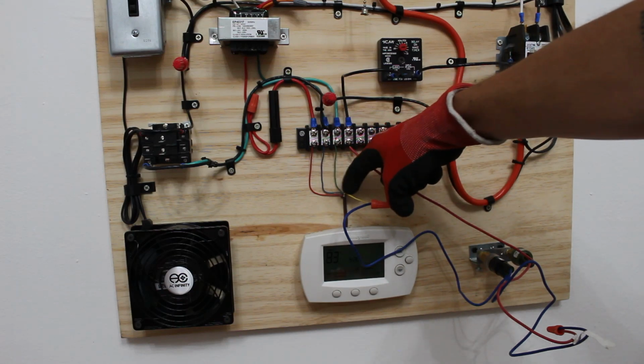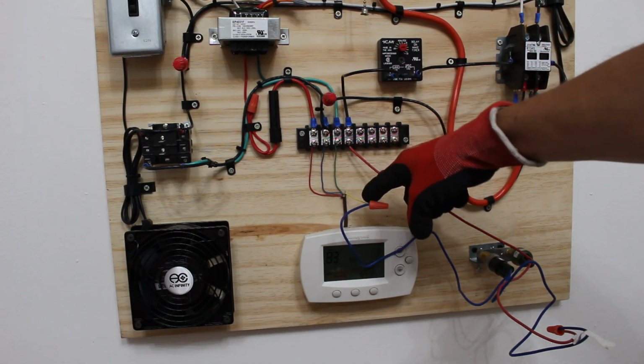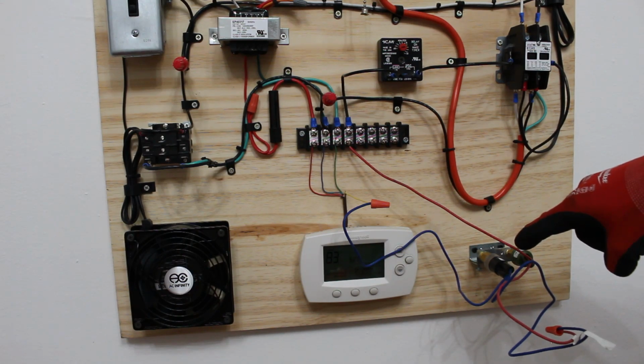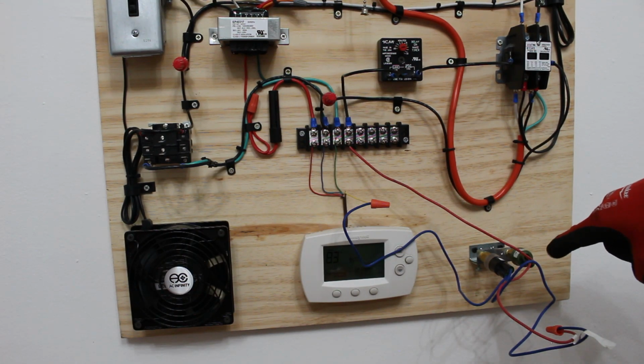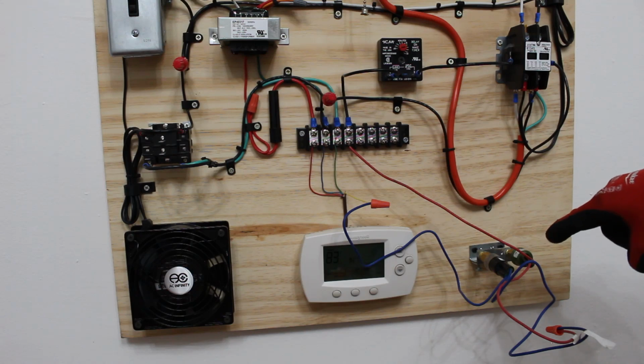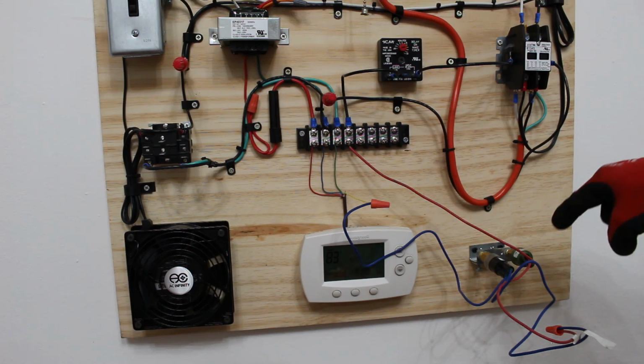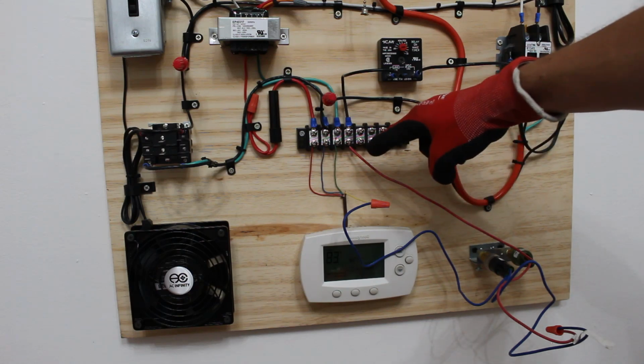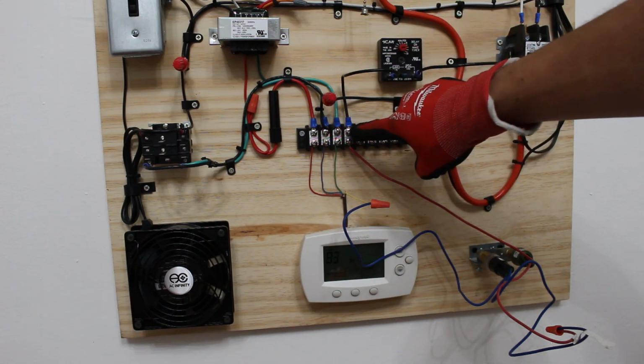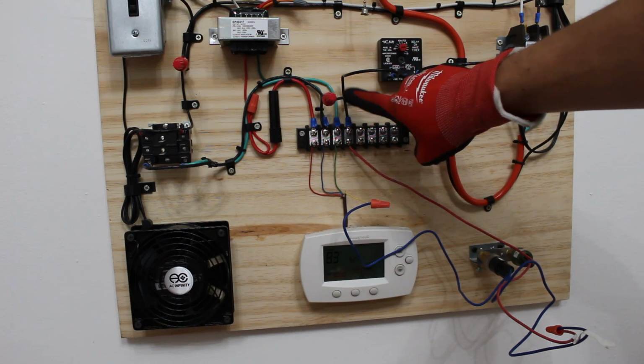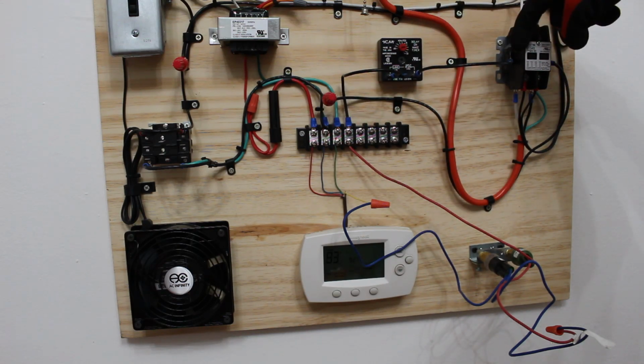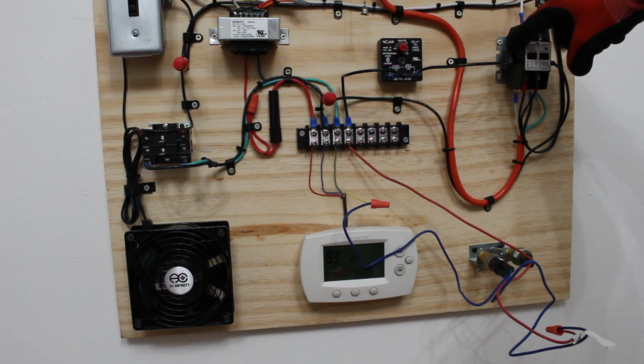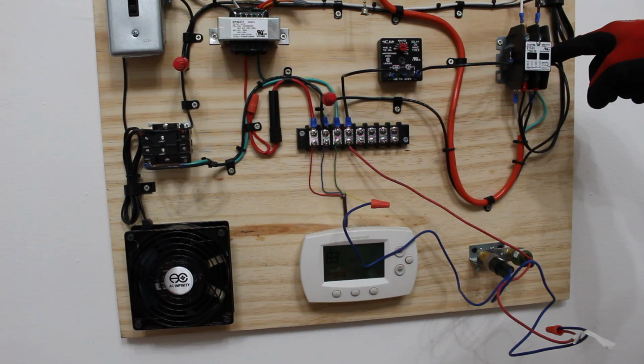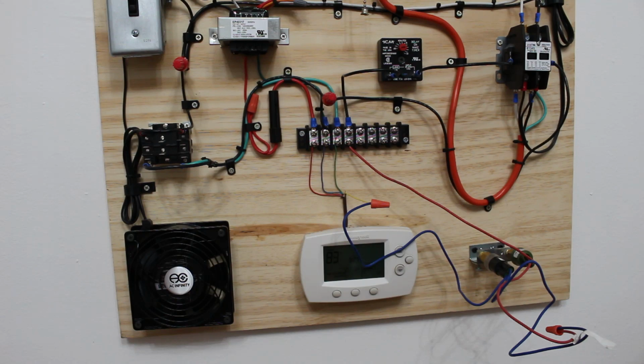So now we have 24 volts on this yellow wire. It's now going to go into the low pressure control, out of the low pressure control, into the high pressure control. And now once we can prove that we have our safeties in good function and everything's okay with the pressures, then it can continue through here and continue with the flow. So what happens in this case is that it goes into our timer, out of our timer to one side of the coil on our contactor, and then the other side of our contactor goes back to common on our transformer, and we can complete the circuit.